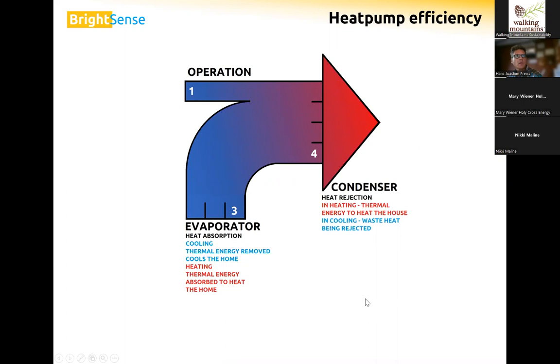If we were to look at this from a cooling standpoint, our usable cooling energy is 3 units. And so 3 units versus 1 for operating the piece of equipment would be a 300% efficiency, or a COP of 3.0. In cooling, we don't care about the hot thermal energy that we are rejecting, unless we were to use it to heat a pool or something like that. But that's a completely different animal.